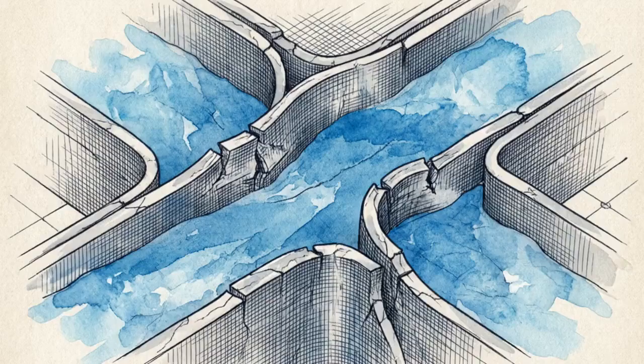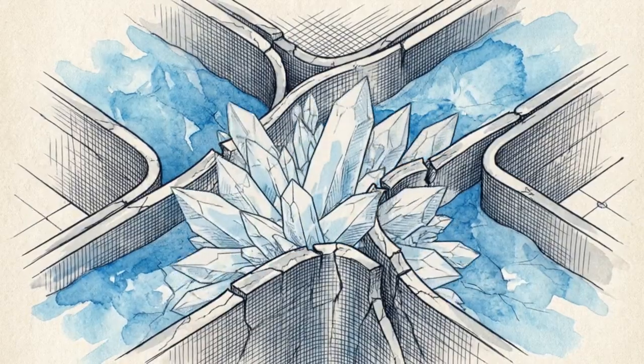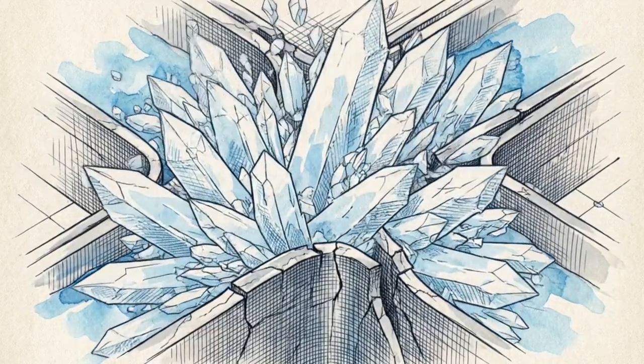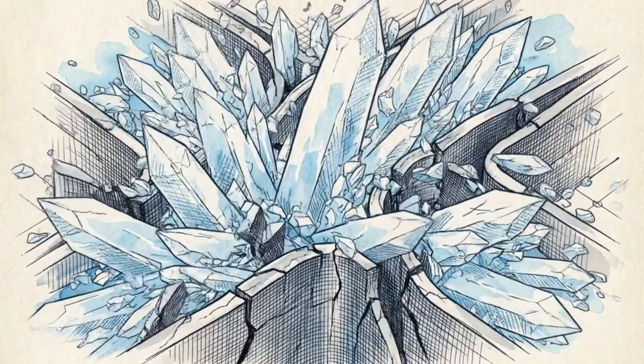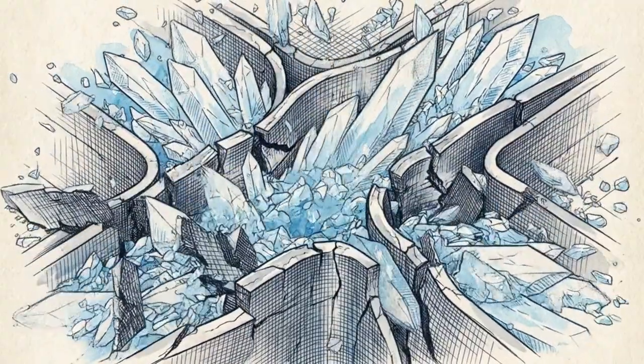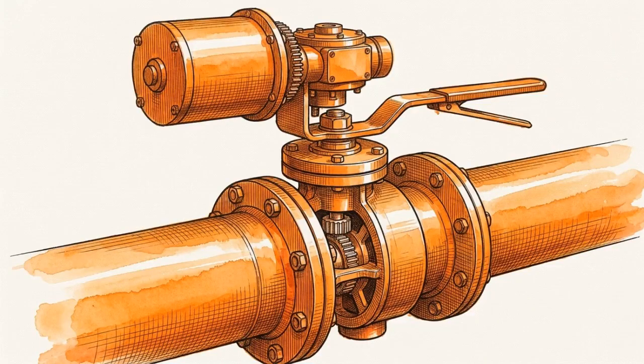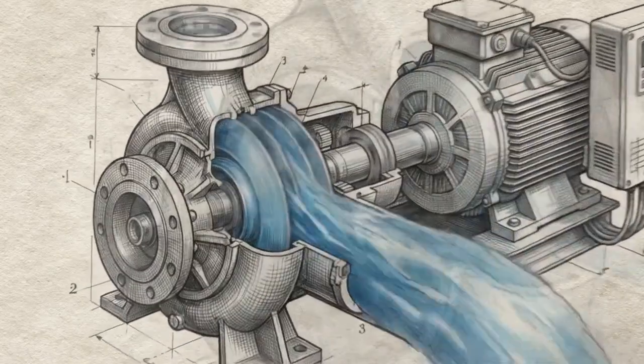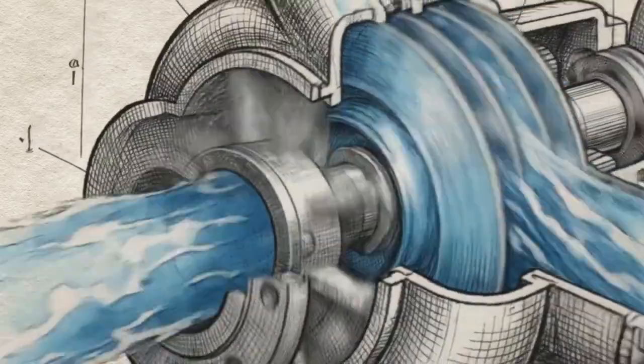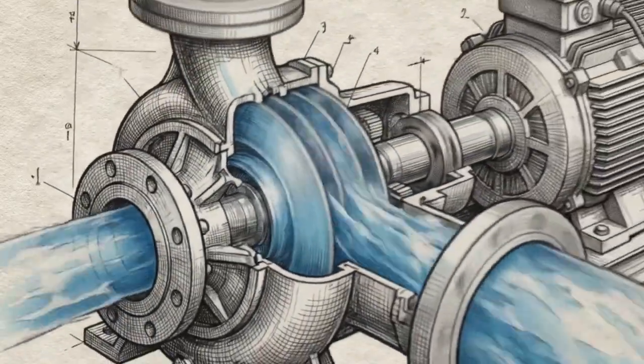If a compressor activates while the water inside the evaporator is stationary, the fluid will rapidly freeze, fracturing the internal plates and destroying the chiller. Down on the mechanical floor, motorized isolation valves rotate open. The variable speed pumps spool up, pushing thousands of liters of fluid through the piping to establish the primary chilled water path.